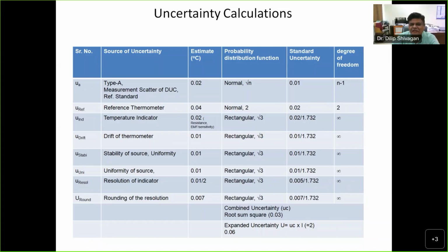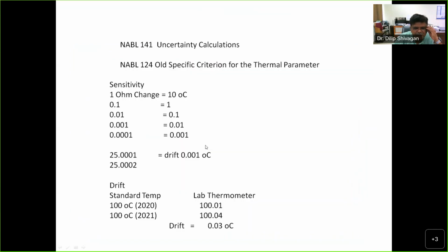Thank you. So we have n minus 1, because if you take out any one measurement, the mod of x minus x bar will go non-zero. Okay, so that way, a reference thermometer will have some certified uncertainty. It is reported as k equal to 2, so divided by k equal to 2, you get the standard uncertainty. Similarly, the temperature indicator also has some uncertainty given. Drift of the thermometer, I will show the example.